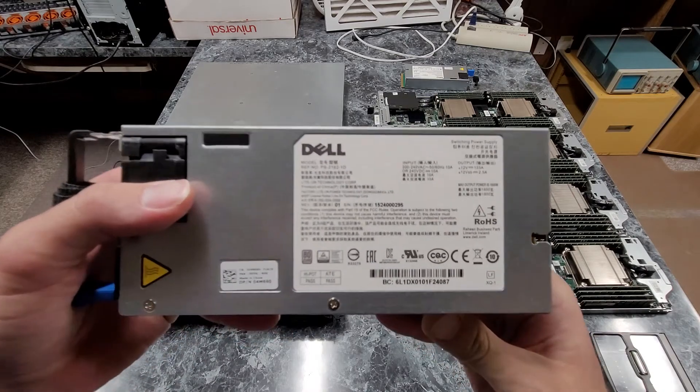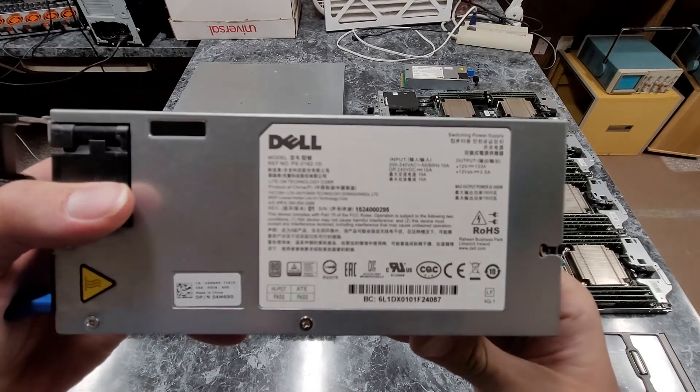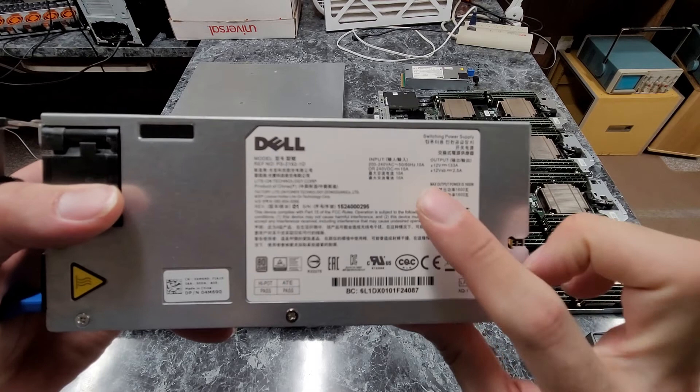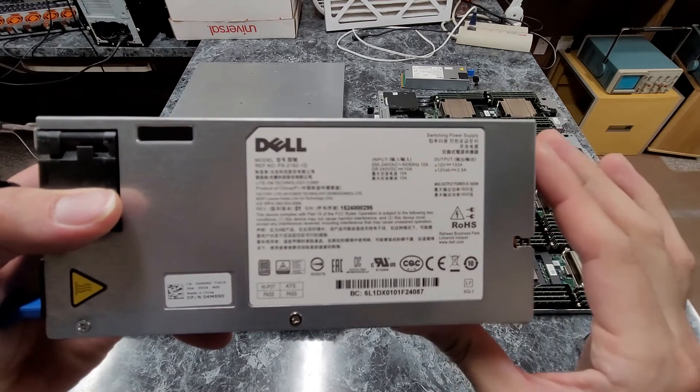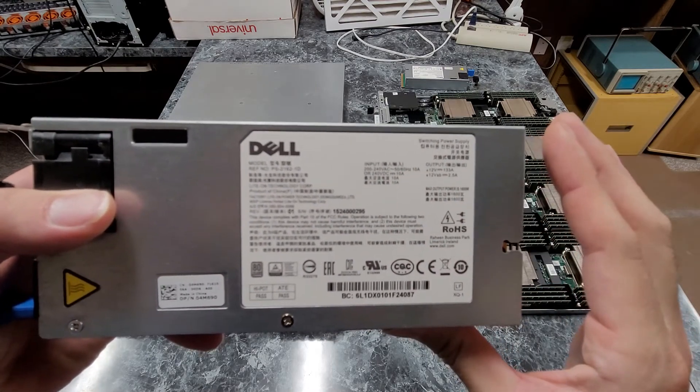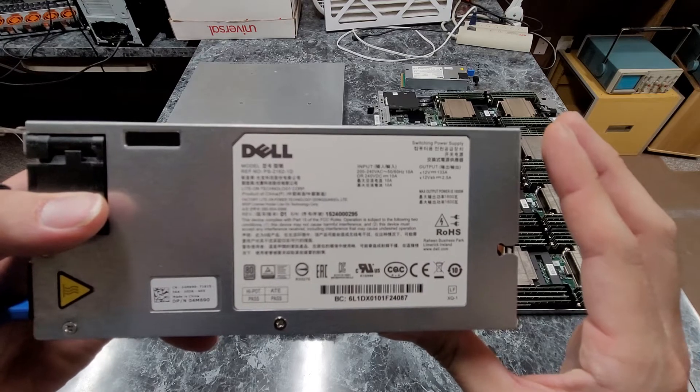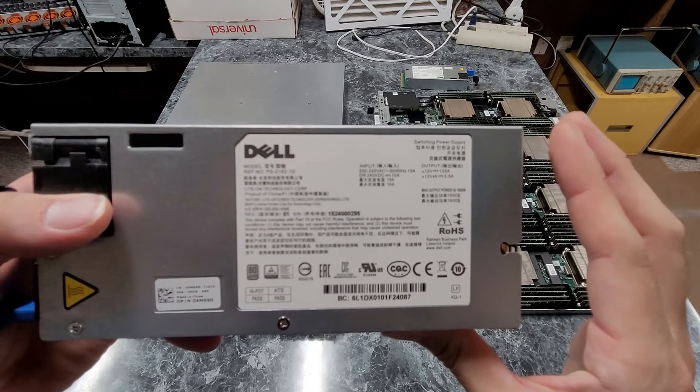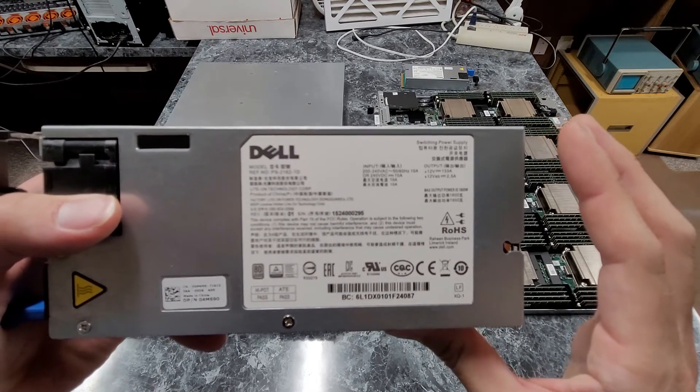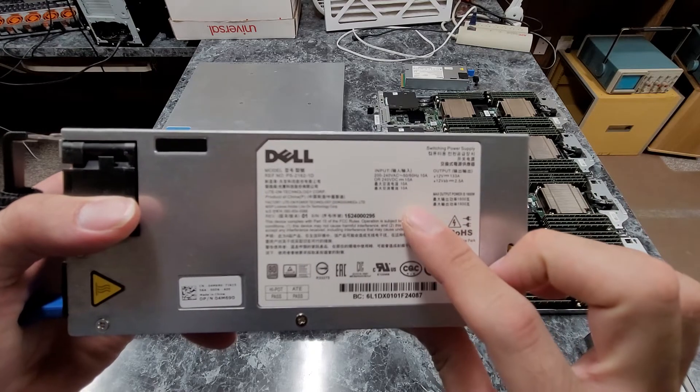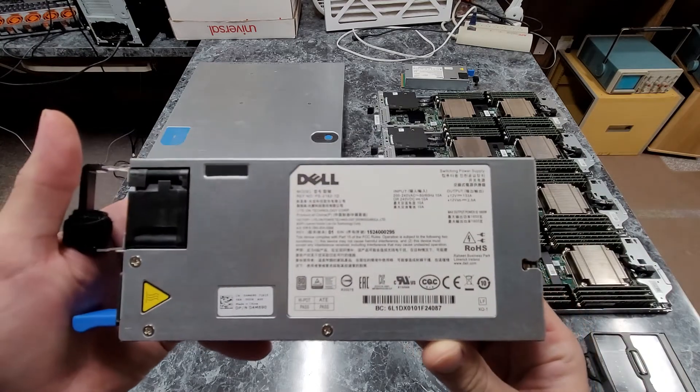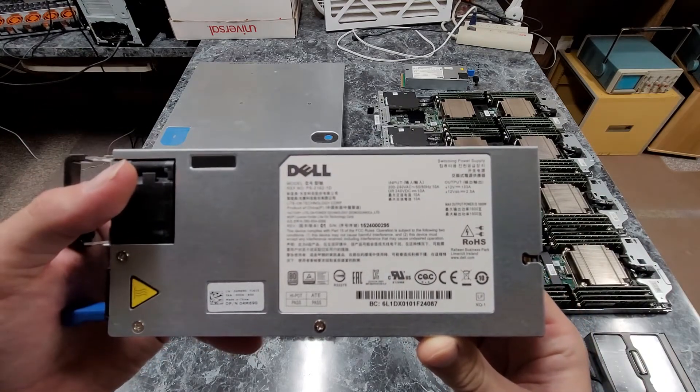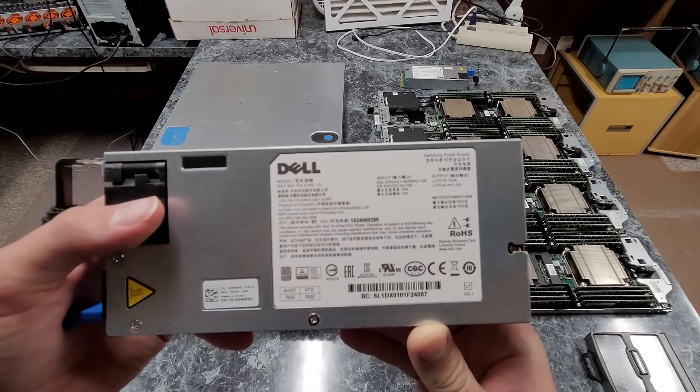One of the downfalls with these power supplies is the fact that they're 200 volt only. So they'll do 200 to 240 volt AC at 10 amps with an output power of 1600 watts per power supply. These are also capable of doing 240 volt DC which I thought was kind of interesting. I don't see too much of that.